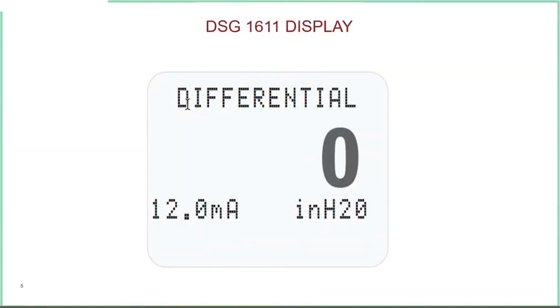This is really what it would look like if it was a 1611, and that's what's in the product now. You can see we recalibrate this at the factory, and it's ready to go when it leaves our factory. It's calibrated, like I said, negative 14 inches of water column up to positive 14 inches of water column. That's why you see down below here it's at 12 milliamps at 0. Because at 4 milliamps, it's a negative 14 inches, and at 20 milliamps, it's a positive 14 inches. So directly in the middle, it would be 12 milliamps. That's pretty much how the display would show out there in the field.